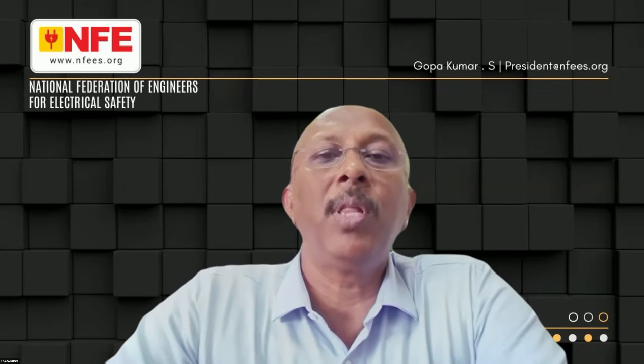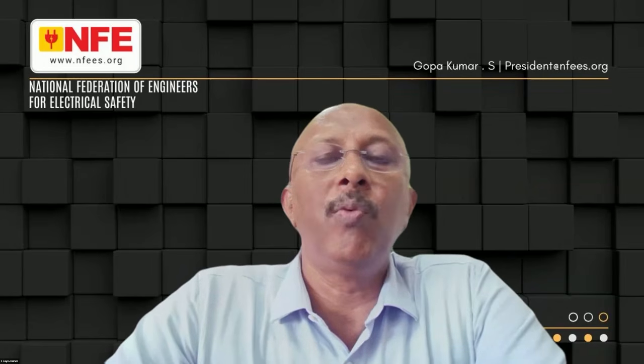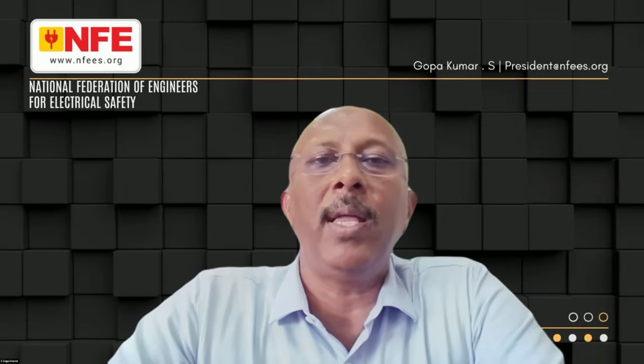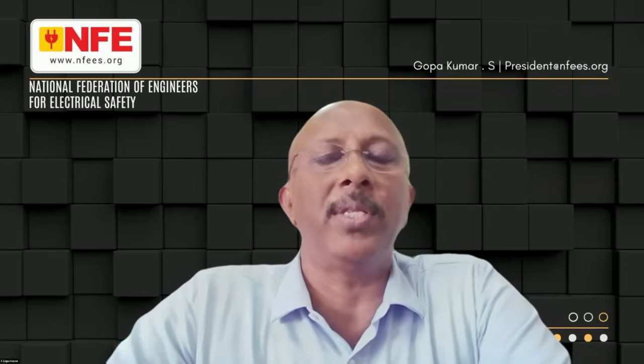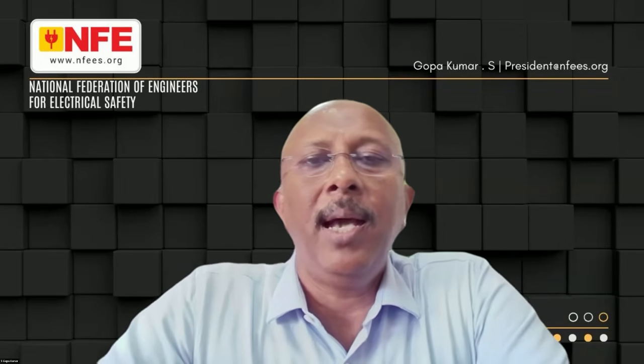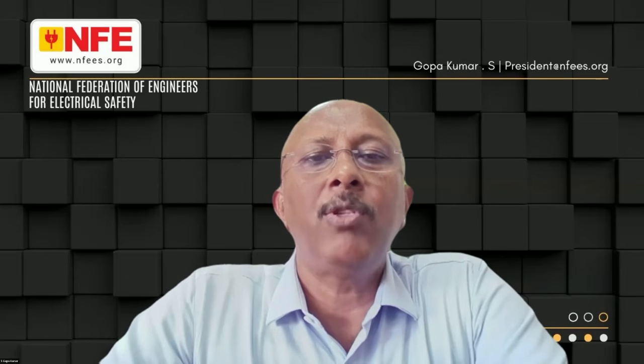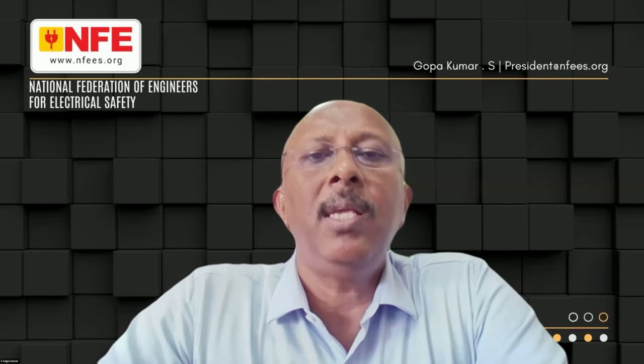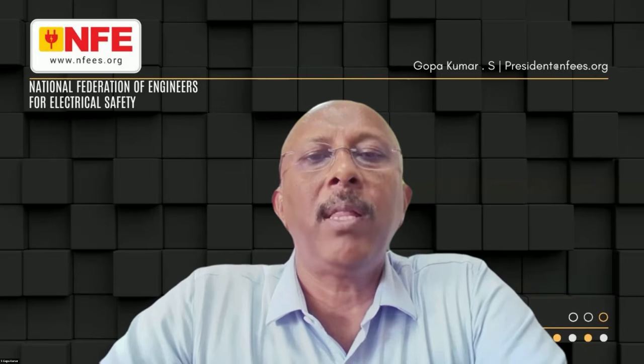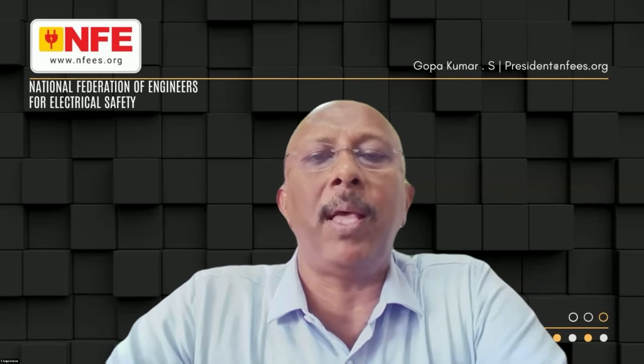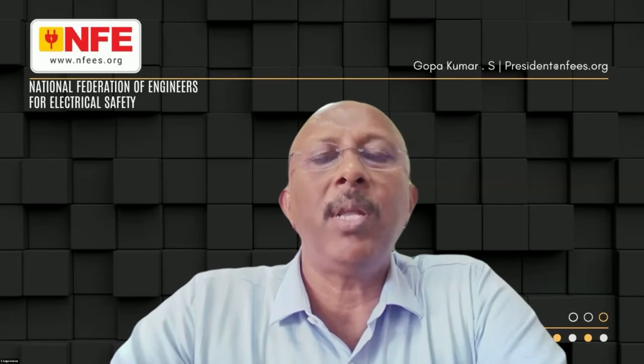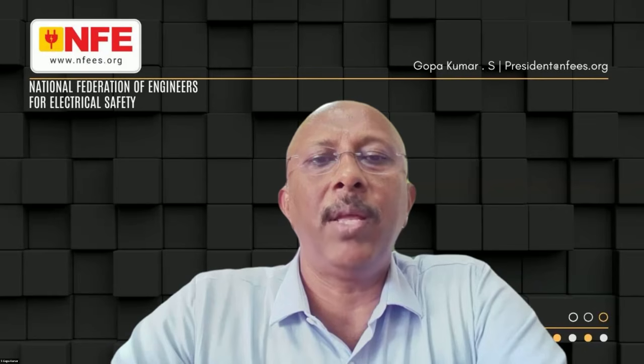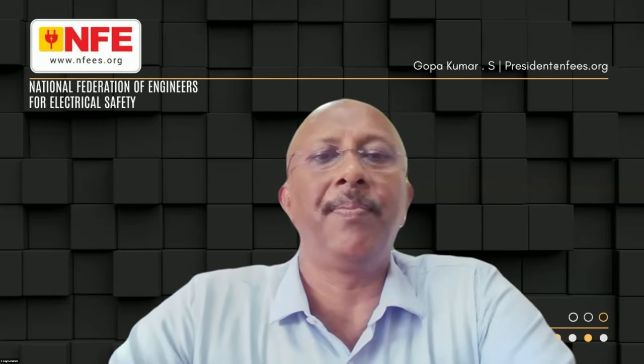Mr. Sunil Kumar, please note that IS 732, which is the standard for electrical wiring, including hospital except medical location, has a clause which says an installation doesn't require its own earth electrode. That means in your hospital, even if there is no earth electrode, your system will work provided you have a very good equipotential bonding system and a TNS supply from a transformer. So earth electrode is not the subject. Achieving safety is a totally different subject.